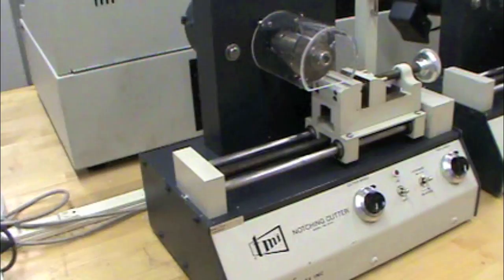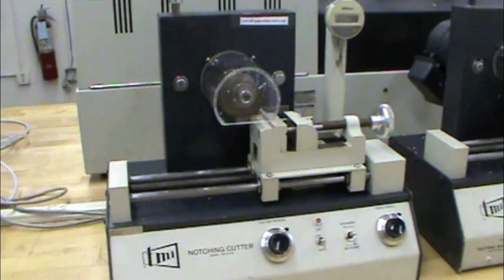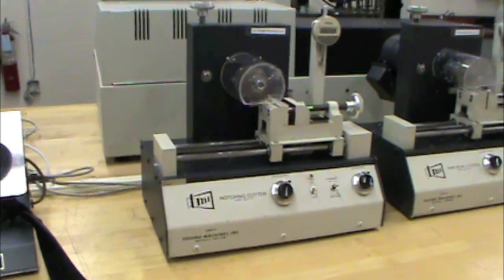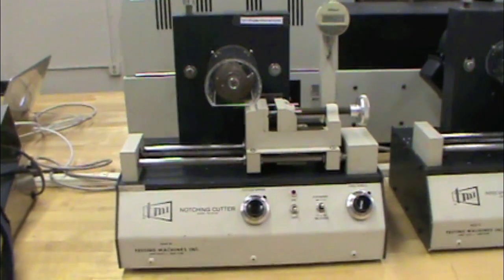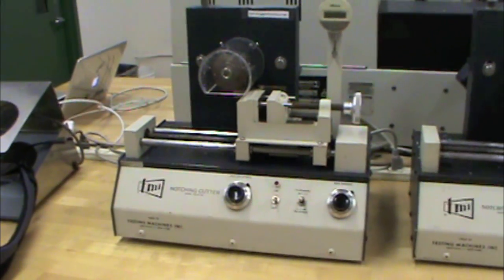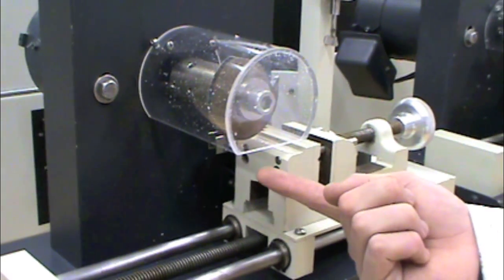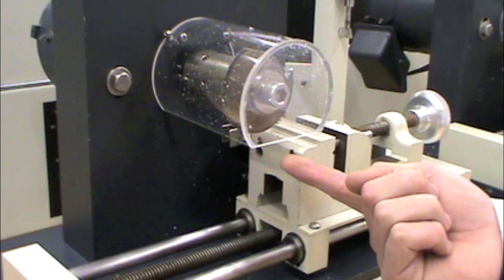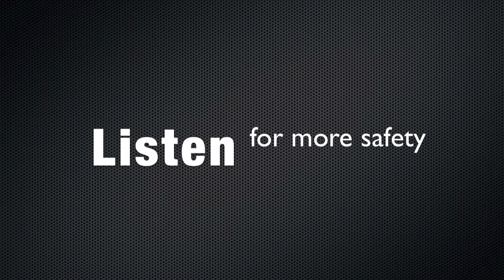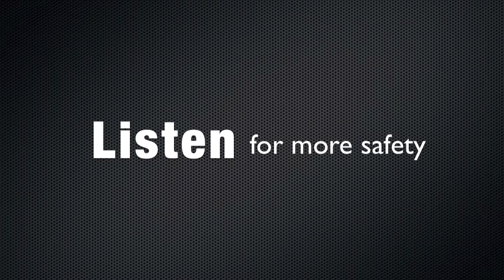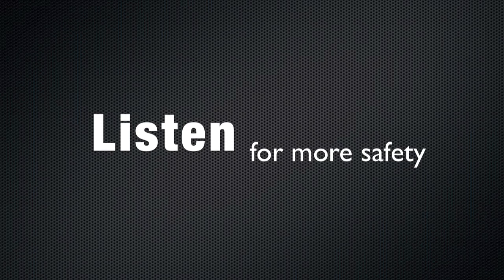You will also be using the Testing Machines Incorporated notching cutter, model 2205, to be cutting notches for the Charpy and Izod notch samples. Be sure to keep your fingers away from the cutting blade and do not reach underneath the safety guard. There will be more safety information offered throughout this presentation, so be sure to keep your ears open. Now that you have the basic safety procedure done, you can now begin testing.